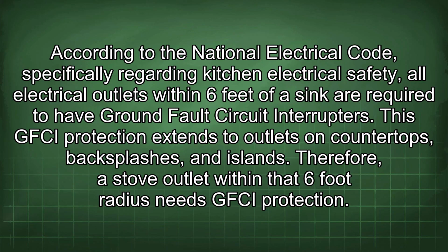According to the National Electrical Code, specifically regarding kitchen electrical safety, all electrical outlets within 6 feet of a sink are required to have ground fault circuit interrupters. This GFCI protection extends to outlets on countertops, backsplashes, and islands. Therefore, a stove outlet within that 6-foot radius needs GFCI protection.